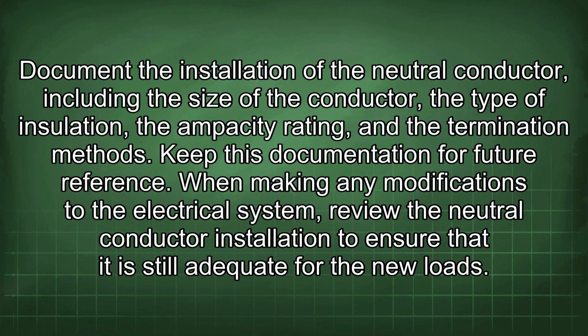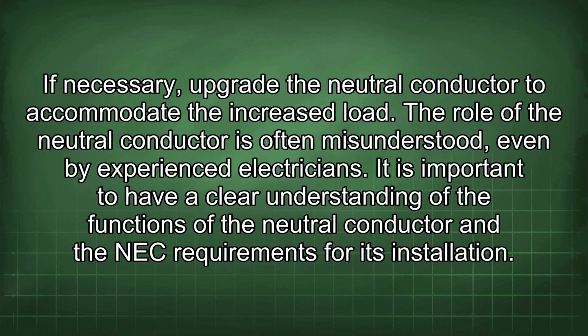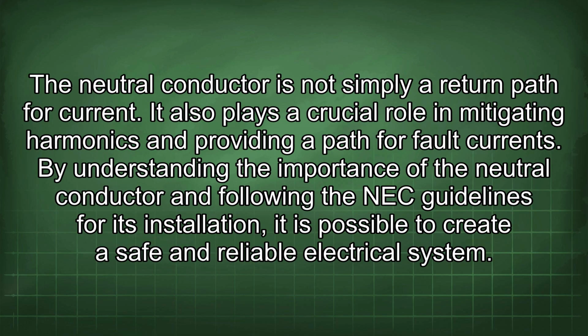When making any modifications to the electrical system, review the neutral conductor installation to ensure that it is still adequate for the new loads. If necessary, upgrade the neutral conductor to accommodate the increased load. The role of the neutral conductor is often misunderstood, even by experienced electricians. It is important to have a clear understanding of the functions of the neutral conductor and the NEC requirements for its installation. The neutral conductor is not simply a return path for current.